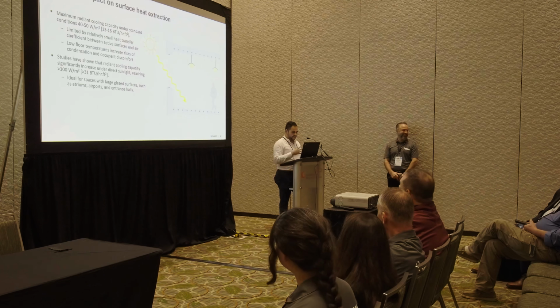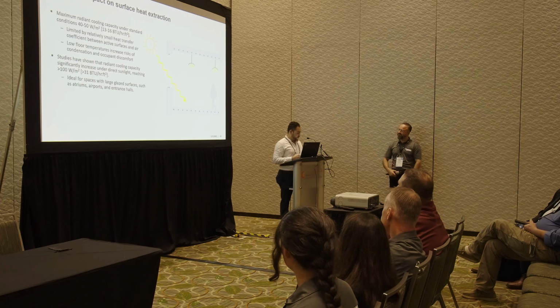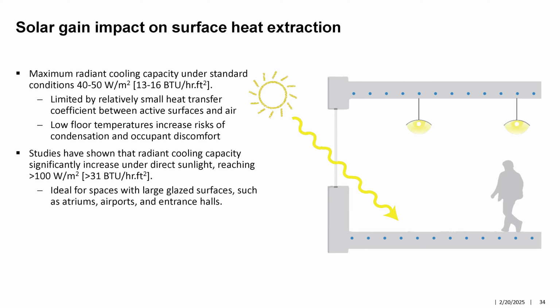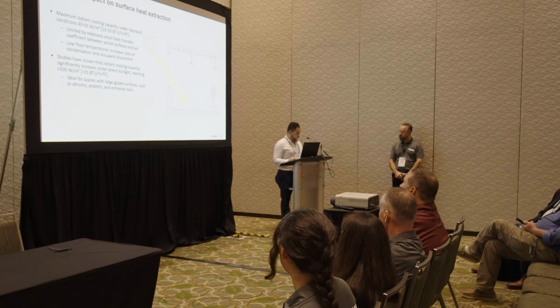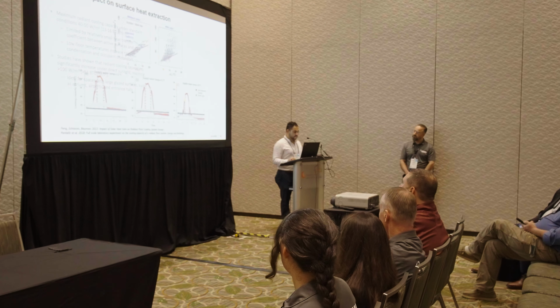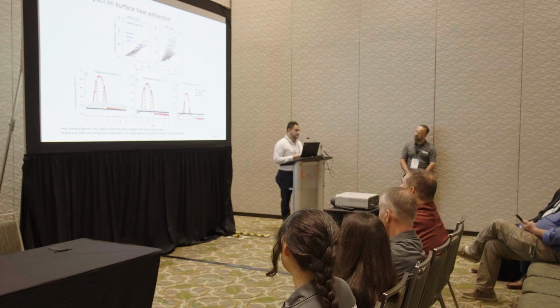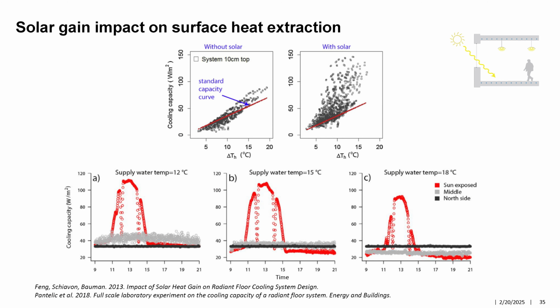So as Saeed was alluding, under standard conditions, the radiant cooling capacity of radiant systems is about 40 to 50 watts per meter square, which is 13 to 16 BTU per hour per square foot. But as soon as the sun starts hitting these radiant surfaces, the capacity increases by doubling or even tripling in some instances. We observed this phenomenon through simulation and laboratory studies.